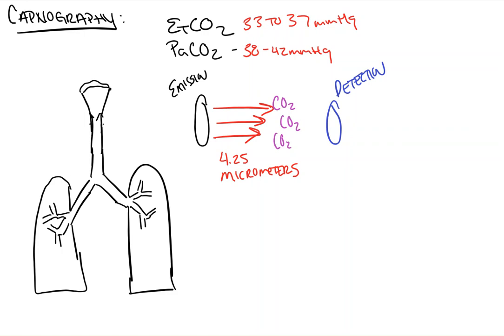As a result, the detector outputs a signal that is proportional to the amount of CO2 present in the sampling chamber as a function of the amount of light that reaches the light detector. The more CO2 present, the less infrared light that gets through to the sensor, the higher the output. The less CO2, the more light that gets through to the detector, the lower the sensor output.